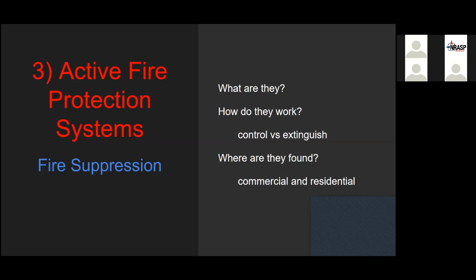So it's important to just understand that even though you have a fire suppression system, it maybe is not designed to put out the fire, even though they often do put out the fires before the fire department gets there. That's not how most of them are designed. Most of them are designed strictly to keep that fire in check until we can get there and complete the extinguishment process.